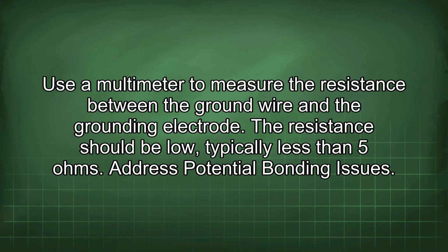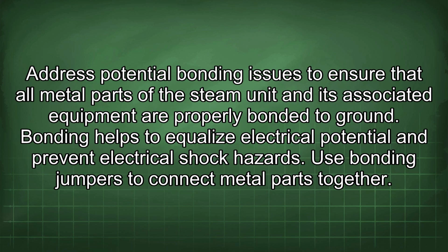The resistance should be low, typically less than 5 ohms. Address potential bonding issues to ensure that all metal parts of the steam unit and its associated equipment are properly bonded to ground. Bonding helps to equalize electrical potential and prevent electrical shock hazards. Use bonding jumpers to connect metal parts together.